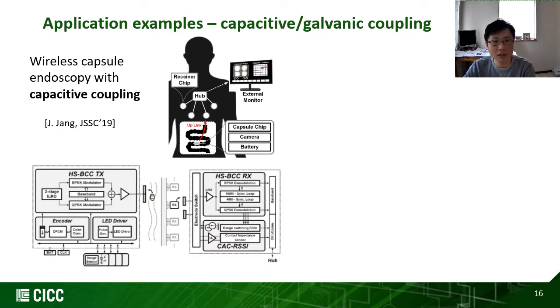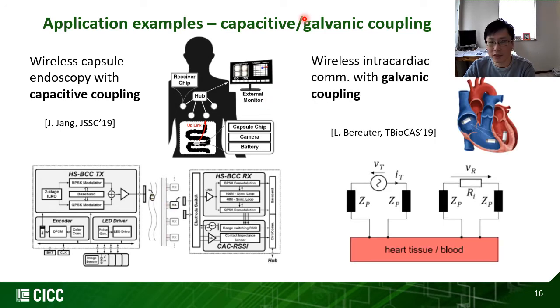So here I would like to show you a few examples using capacitive and galvanic coupling in implantable communication. On the left, you can see wireless capsule endoscopy using capacitive coupling. The ingested pill inside the digestive tract sends the signal via the tissue, to be received by the external receiver attached on the body. On the right side, we can see wireless intra-cardiac communication using galvanic coupling. Several implants are placed in different parts of the heart, and they need to communicate with each other. Their approach is to use differential electrodes and propagate the signal through the conductivity of the tissues.